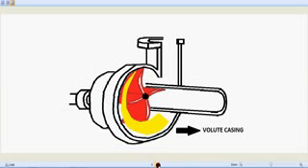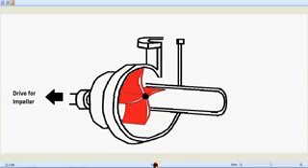So what happens is that at the top, at this point, the velocity of the oil will be much higher and the pressure will be less, but as it comes down, as the area increases, velocity gradually decreases because the area is slowly increasing, and as the area is increasing, thereby the pressure increases, so we'll get a pressured discharge over here. Okay, so that's the significance of the volute casing.